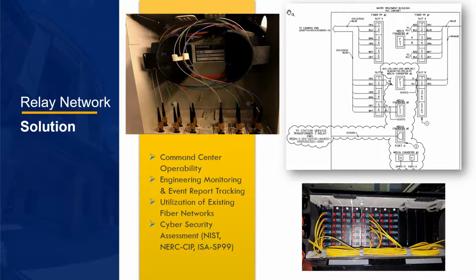This allows for certain personnel to access the event reports and metering data without access to the breaker operation, whether accidentally or intentionally. Adding such networks can be relatively straightforward, and if existing fiber infrastructure is available for use, as in this case, connecting to the devices outside of the central location is easily manageable with the use of media converters or additional switches. One thing to highlight when building or adding to a network, especially when connecting with outside networks, is a cybersecurity assessment is imperative to ensure protection from the outside threats and compliance with standards like NIST, NERC CIP, and ISA 99.